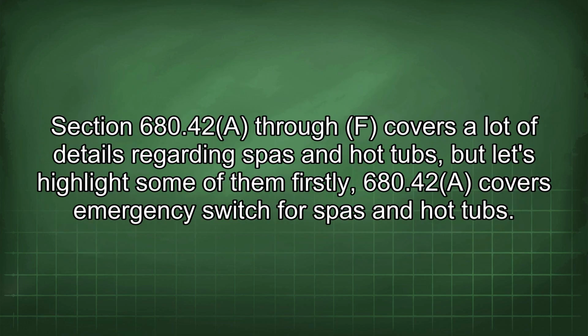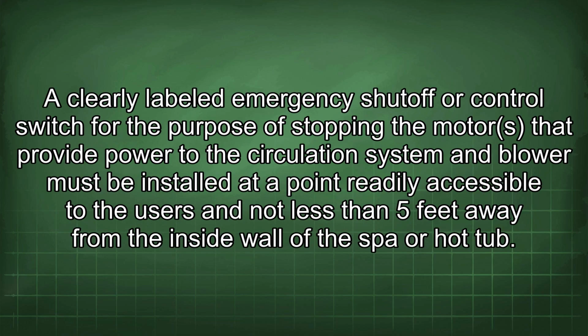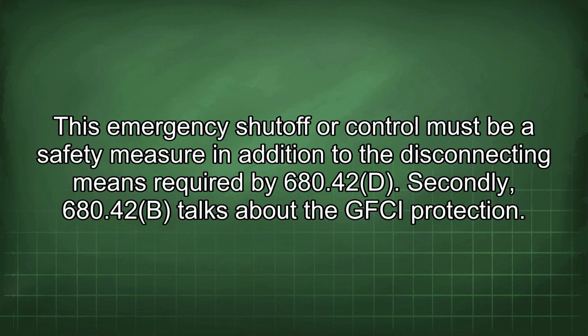Section 680.42(A) through (F) covers a lot of details regarding spas and hot tubs, but let's highlight some of them. Firstly, 680.42(A) covers the emergency switch for spas and hot tubs. A clearly labeled emergency shut-off or control switch for the purpose of stopping the motors that provide power to the circulation system and blower must be installed at a point readily accessible to the users and not less than 5 feet away from the inside wall of the spa or hot tub. This emergency shut-off or control must be a safety measure in addition to the disconnecting means required by 680.42(D).